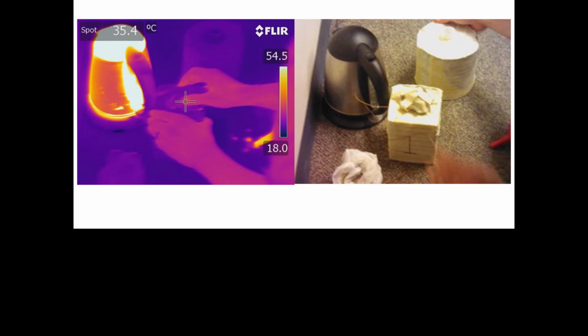Why is the camera showing me this difference if I tell you that the temperature is more or less the same? It's shiny metal and emissivity. Right, this is shiny metal, so it's emitting very little light. So the camera, I think, the way a thermal camera works is it looks at how much heat comes into it and says, oh, if I got this much heat, therefore I have this temperature. It's a pretty dumb thing, and I paid like $150,000 for one of those. I cannot believe it. But we're trying to spend that much money again on something else.